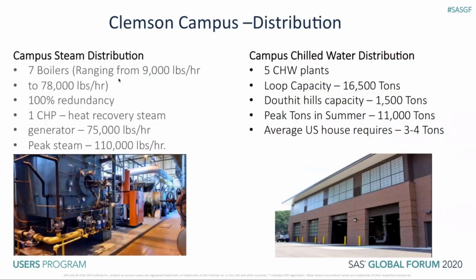So on Clemson campus, we have various distribution networks. The primary ones are steam, chill water, and electric distributions, which are key distribution networks. Just give a brief overview of steam distribution network. We got about 7 boilers ranging from 9,000 pound-hour to 78,000 pound-hour steam. We got 100% redundancy in our steam distribution system. We got 1 CHP heat recovery steam system and a generator with 75,000 pounds per hour through that heat recovery steam generation. And our campus peak demand or peak steam load is about 110,000 pounds per hour.